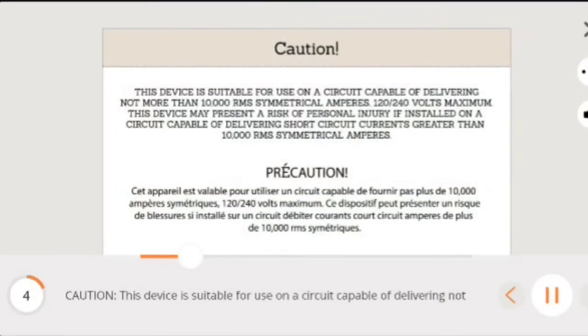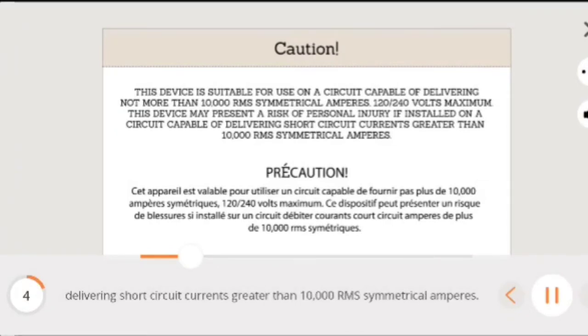Caution, this device is suitable for use on a circuit capable of delivering not more than 10,000 RMS symmetrical amperes, 120-240 volts maximum. This device may present a risk of personal injury if installed on a circuit capable of delivering short circuit currents greater than 10,000 RMS symmetrical amperes.